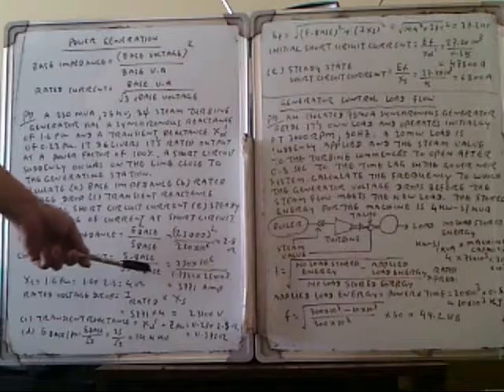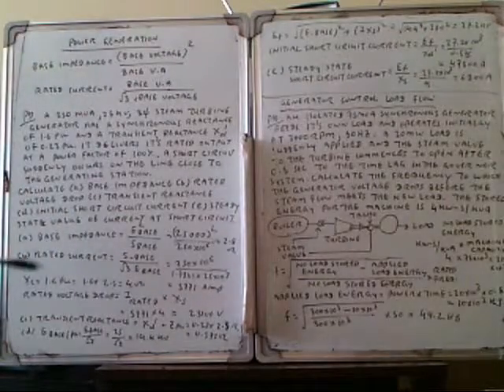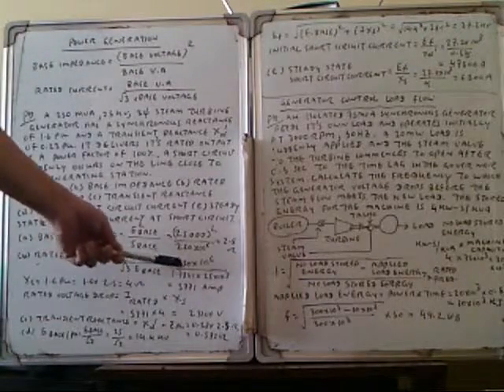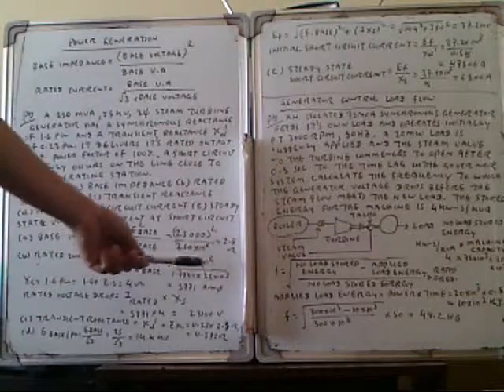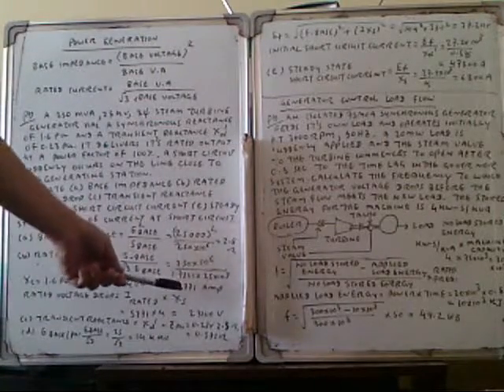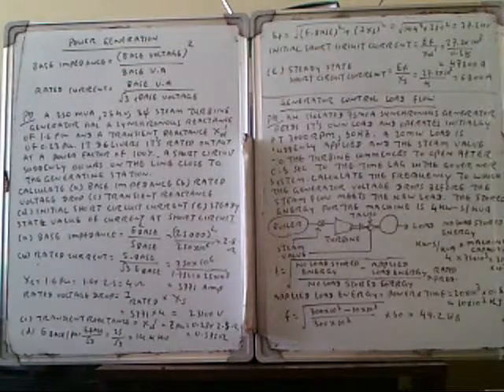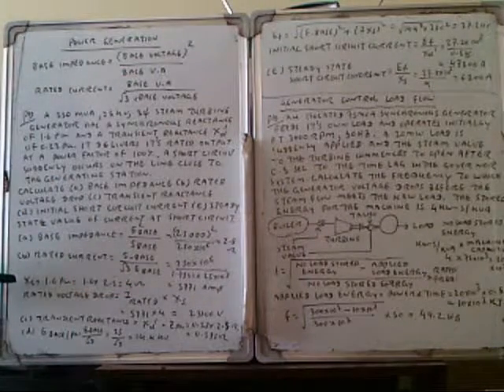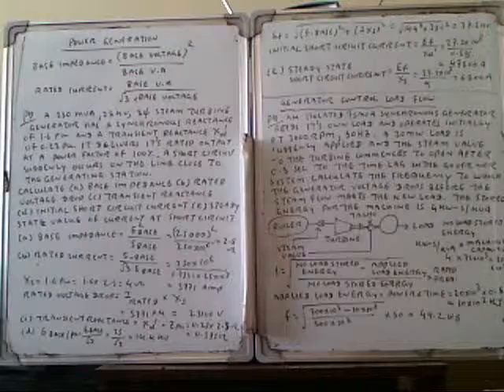We can also calculate the rated current. The base MVA is 250 × 10⁶, divided by root 3 times the base voltage of 25 × 10³, giving a rated current of 5,771 amperes.